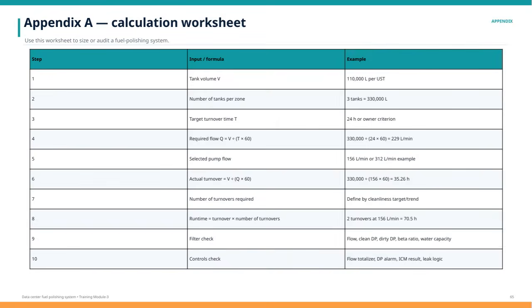Now, let's take a closer look at Appendix A, which is a calculation worksheet designed to help size or audit a fuel polishing system. This worksheet guides us through a step-by-step process using specific input values and formulas. We start with the tank volume, represented as V. In the example, the tank volume is 110,000 liters per underground storage tank. Next, we account for the number of tanks in a zone. Here we have 3 tanks, totaling 330,000 liters.